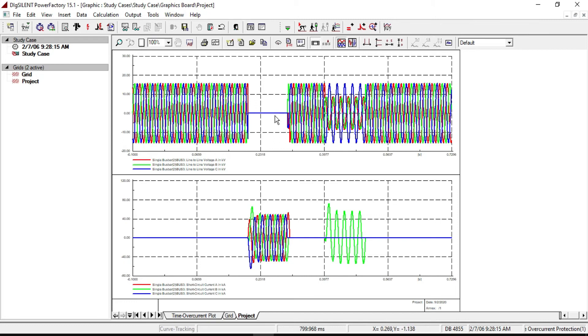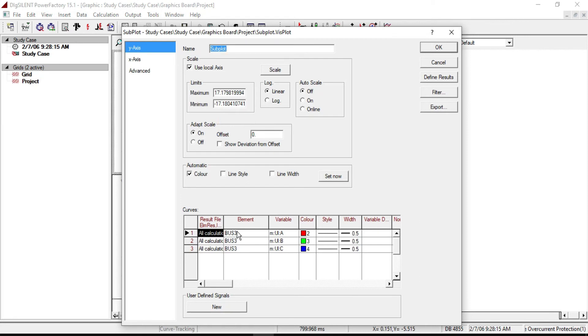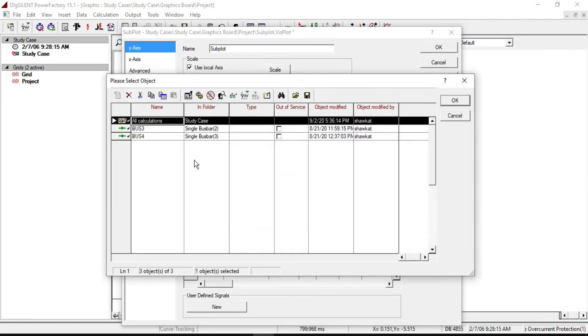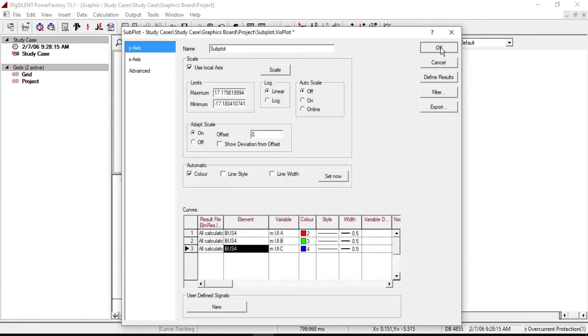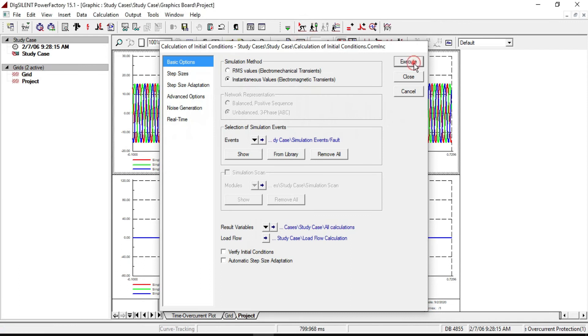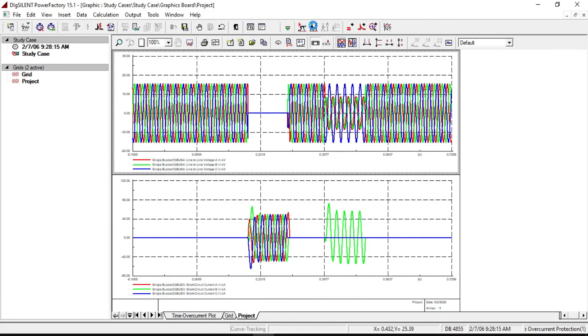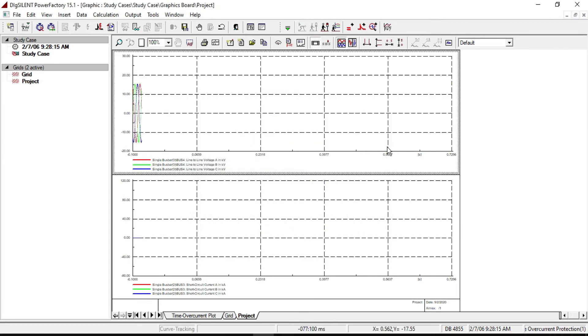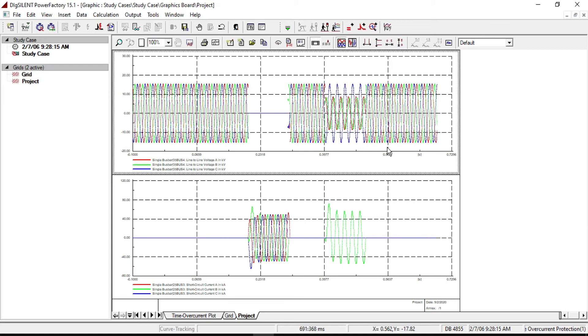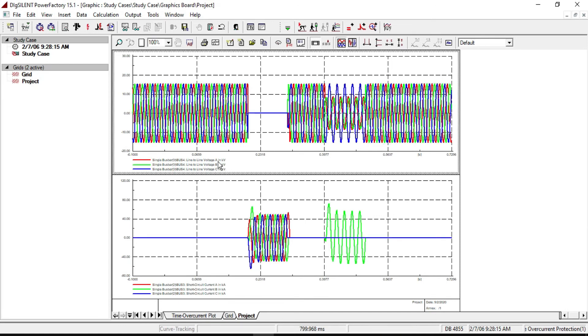Let's see the voltage waveform plot on bus 4. Double click here and from the element select bus 4 for all phases, then click OK. As expected, the voltage waveform is actually the same as bus 3: fault occurring at 0.2 and cleared at 0.3 seconds, then a single phase to ground fault from 0.4 to 0.5 seconds.